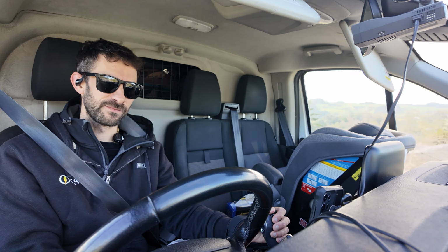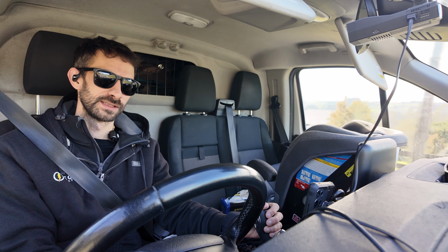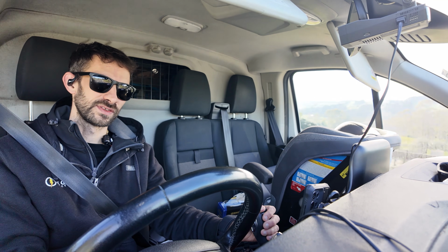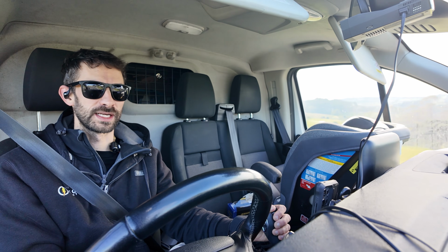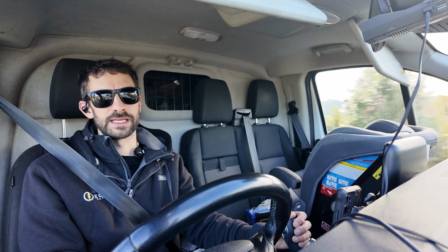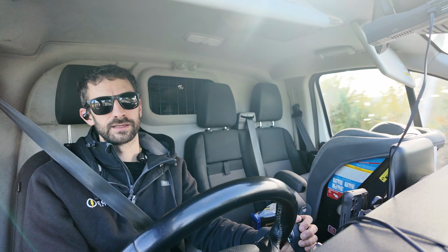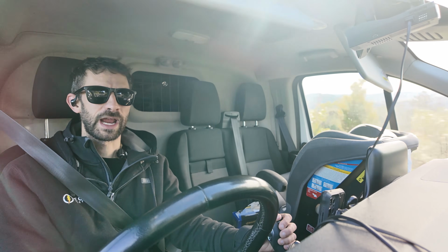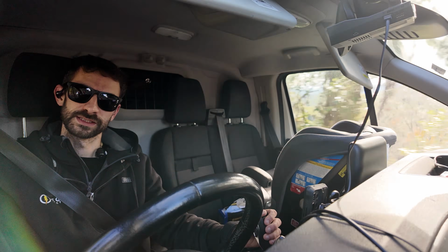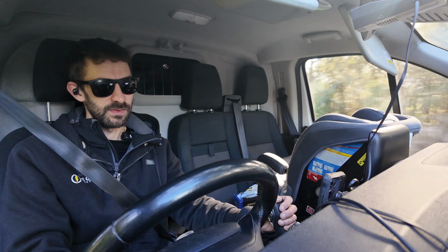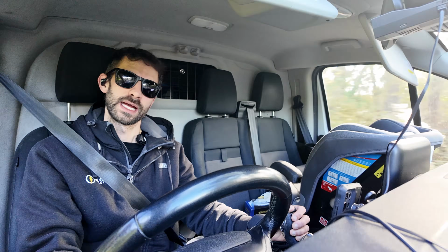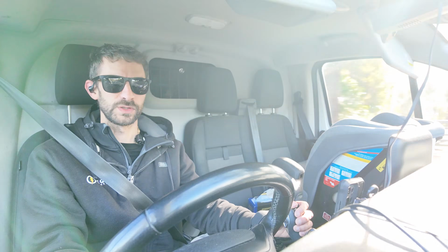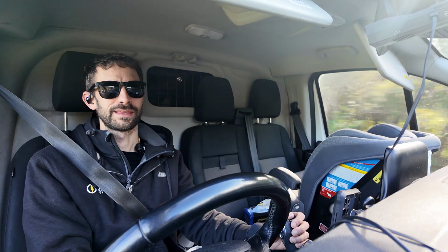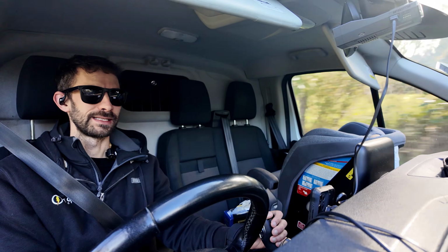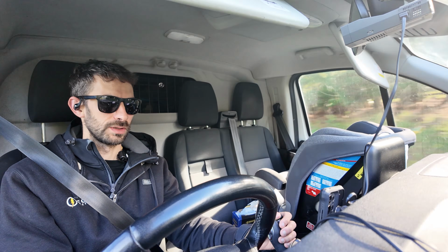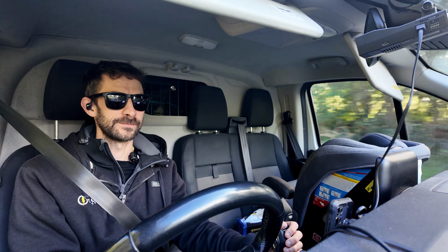It's not one that I've really understood, because you could have a situation where the fault is running through an RCD. The voltage created by a loss of neutral, the current that's generated from that fault runs through the neutral in and then back out through the other side of the neutral and then builds up on the other side of that. So if you get a shock from that, the fault path is not creating an imbalance in the RCD, so you don't get protection against it.